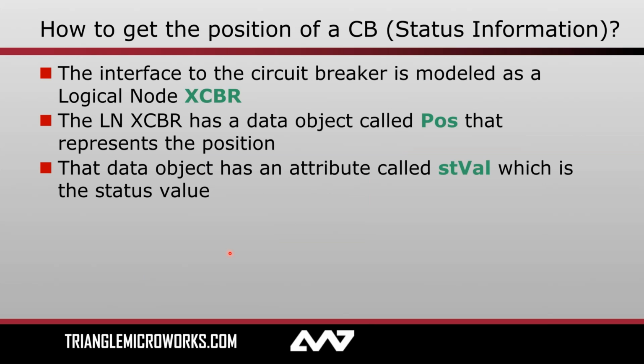Now, before we get into how data is actually transferred, let's set up a little bit of an example. Let's say we have a logical node, XCBR. As we spoke about last webinar, X in the logical node names refers to an interface, and CBR refers specifically to the interface to a circuit breaker. Now, of course, this logical node will have child data objects, for example, Pos, or position. And that in and of itself will have child data attributes, for example, stVal. Let's say we want to find the status of the breaker by determining the value stored in stVal, or the status value of that breaker.